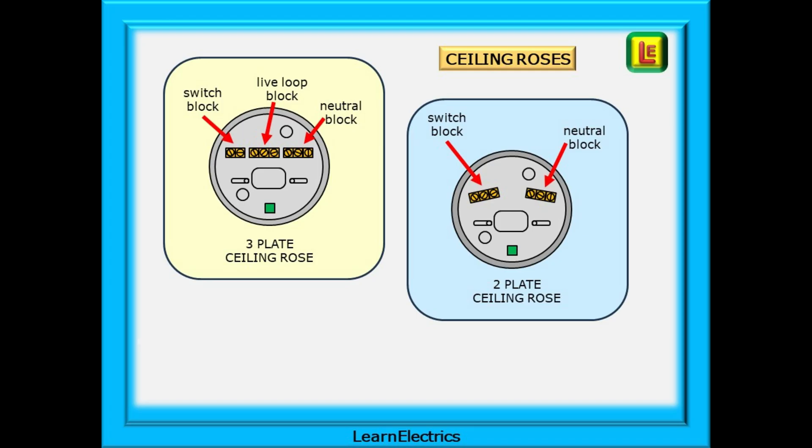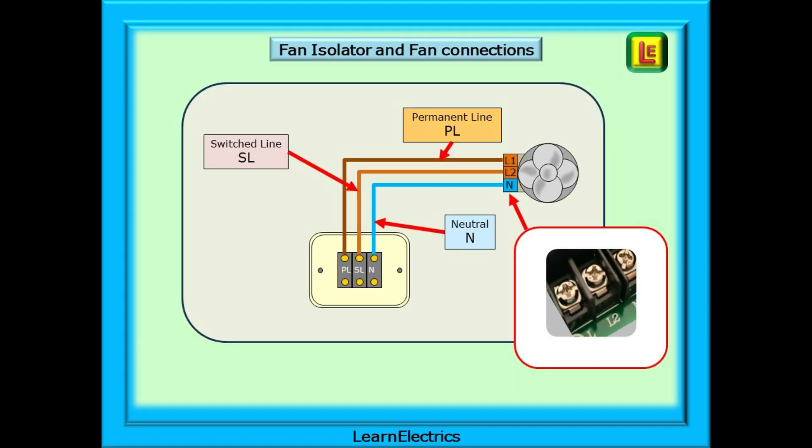We'll be using three pole fan isolators with connections for a permanent line, a switch line and a neutral conductor. This is to enable the fan to be completely isolated electrically when carrying out cleaning or mechanical maintenance.